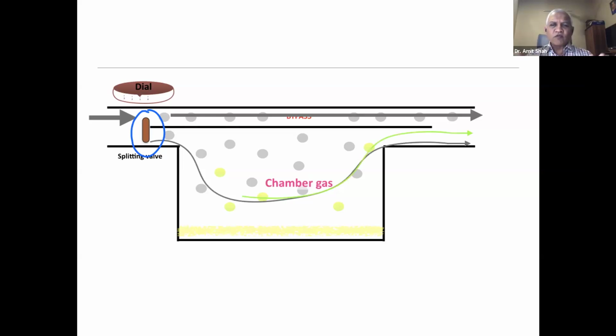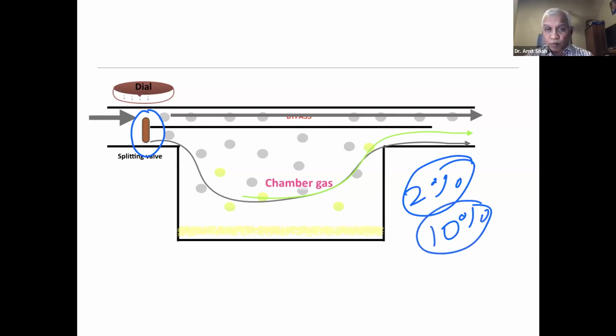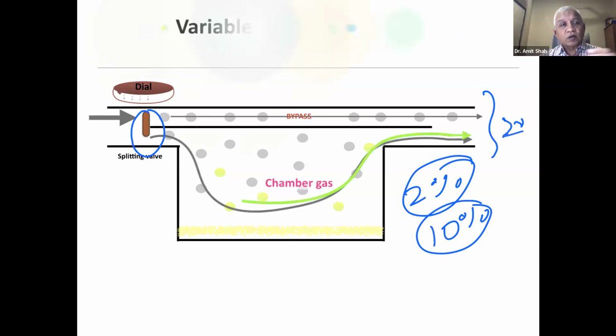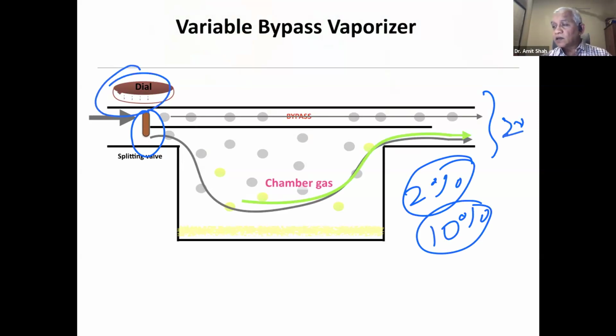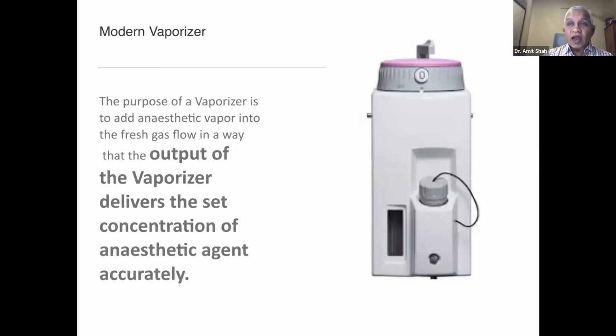Okay. This would be roughly, just for an example, not exact, but if you want 2% concentration, it will pass only 10% of flow through this vaporizing chamber to take the vapor, so that the output is 2%. Okay. If you want more, like the dial we have converted to 4, then the splitting valve will allow more gas to pass through the vaporizing chamber. So this is how a variable bypass vaporizer will work. And that is our modern vaporizer. The purpose of the vaporizer is to pass fresh gas flow in a way that the output of the vaporizer delivers the set concentration which we have set, or which we desire to pass.